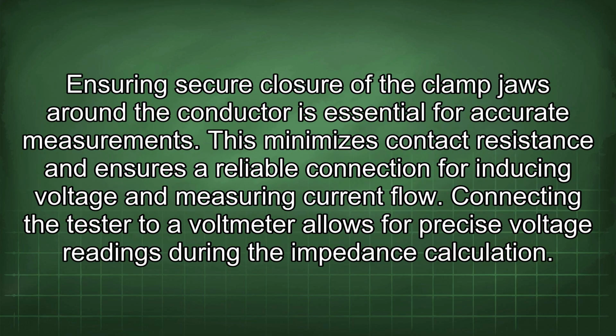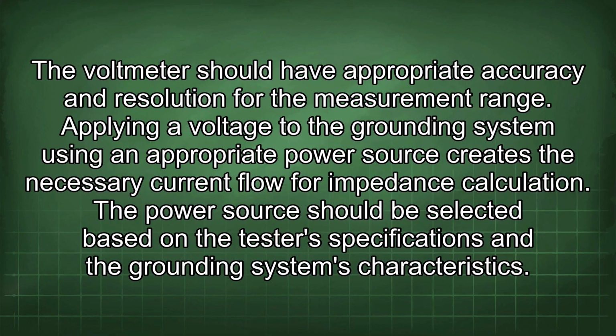Ensuring secure closure of the clamp jaws around the conductor is essential for accurate measurements. This minimizes contact resistance and ensures a reliable connection for inducing voltage and measuring current flow. Connecting the tester to a voltmeter allows for precise voltage readings during the impedance calculation. The voltmeter should have appropriate accuracy and resolution for the measurement range.